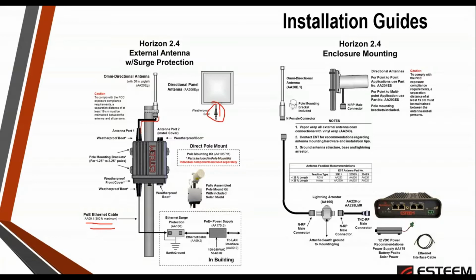As I mentioned, down at the lower end, this works into the surge protector: the Ethernet cable gets clamped inside the surge protection device, and the shield coming off the radio wraps around the outside and goes to earth ground. The surge protector and the shield go to the same earth ground potential, so that if there's a nearby strike or a buildup of energy on the case itself, it can pass to earth ground without damaging the radio.